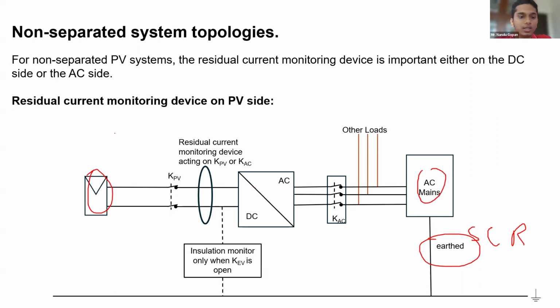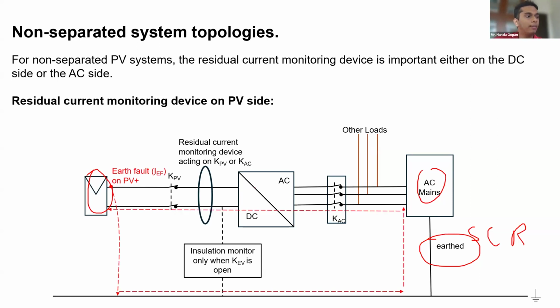So in this case, if there is any fault on the solar PV side, the current travels to the system referencing conductor on the discom's transformer. It will travel through the system referencing conductor, go to the neutral of the conductor, and go back to the source. So in this case, you are supposed to have a residual current monitoring device, and this residual current monitoring device will act on either KPV or KAC. Depending on the topology, wherever the disconnection is required, it can happen.